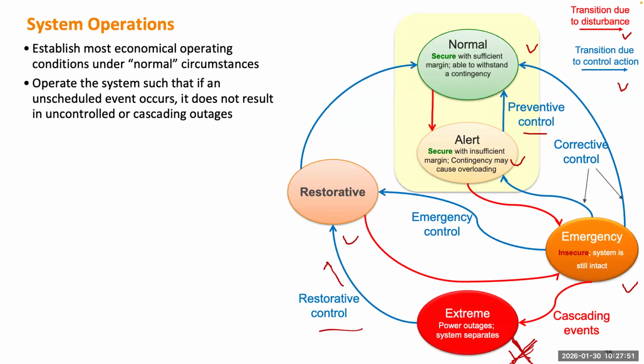So that's definitely why, if you avoid this one from happening, you always make sure the system is changing among the normal state, alert state, and sometimes emergency state. Even in emergency state, as long as it doesn't damage anything, it's still okay. So this is the number one thing for the operator to avoid, right? Never make the system enter this state. That's basically equivalent to power outages and blackouts. Once the system enters that state, it's out of your control.